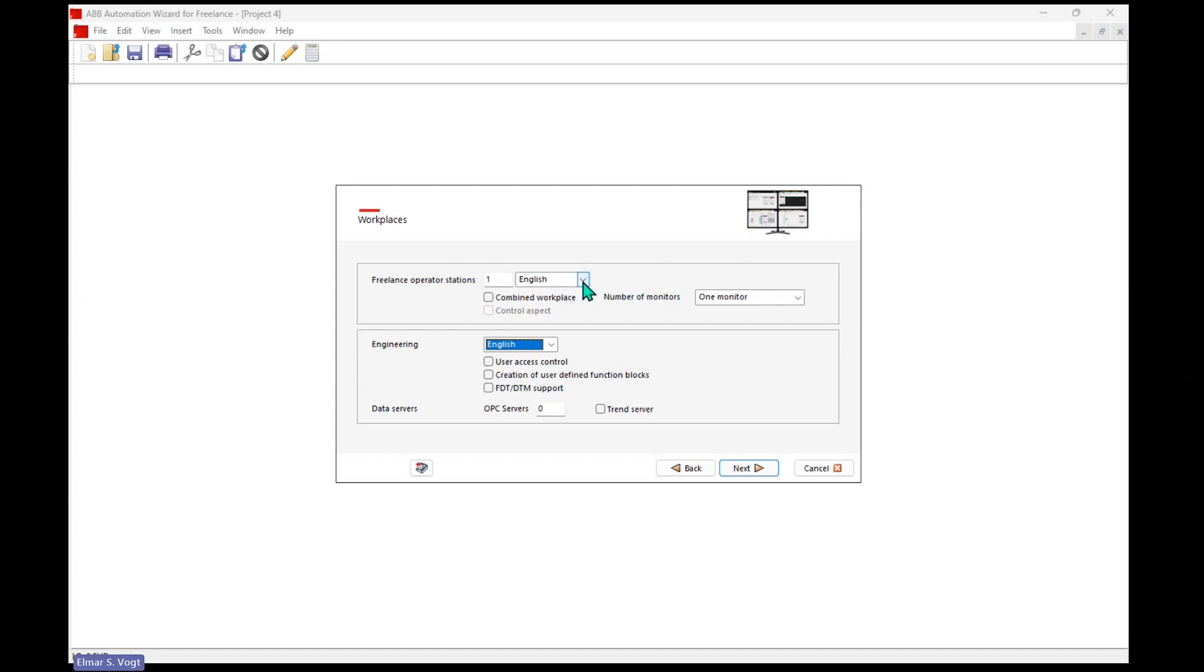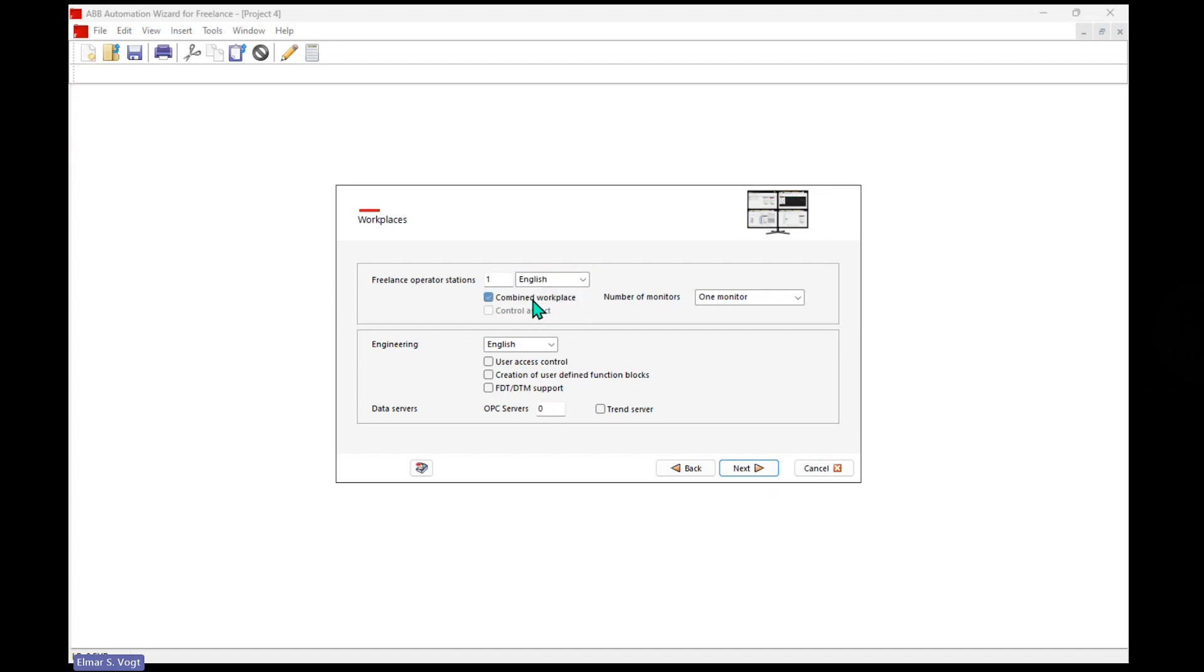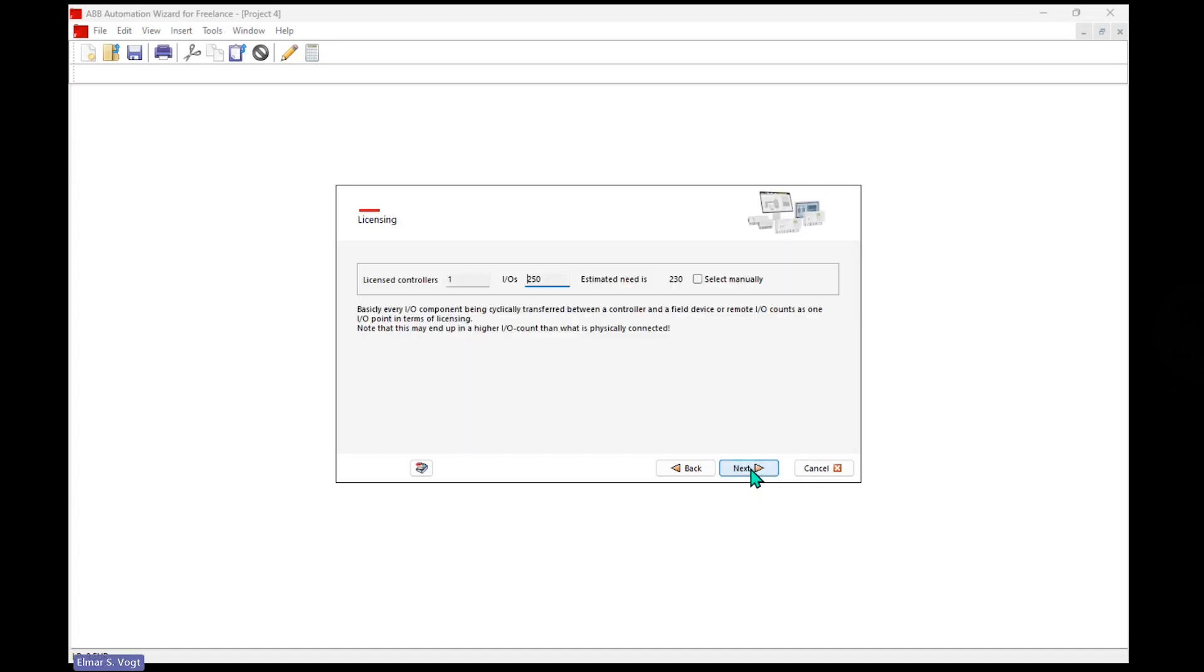We want to go with English. No need for other languages now. And we want to have a combined, just one PC that runs operator interface and engineering tool. It should have a user access control, creation of user-defined function blocks, FDT DTM for field devices from Profibus, and I want to have a redundant OPC UA server within here.